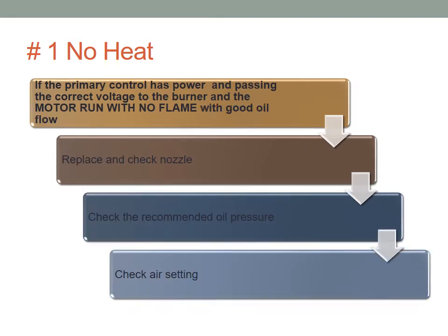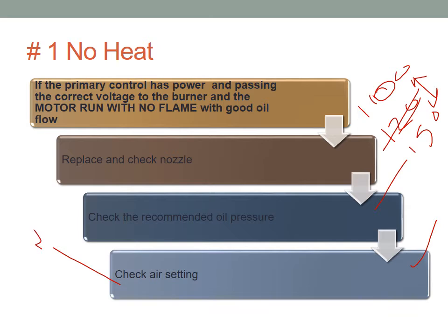So check no flame with oil. Replace and check the nozzle. Check the oil pressure. We said it's usually between 100 and 150, could be 120, 150, but check that you have the right oil pressure. Check the air setting. Do we have the right setting for the air? Is it clogged? Is it open all the way? What happens if the air is open all the way? That's a big possibility. You're blowing the flame away and it's not containing flame. So you want it to be not too much, and not closed also.